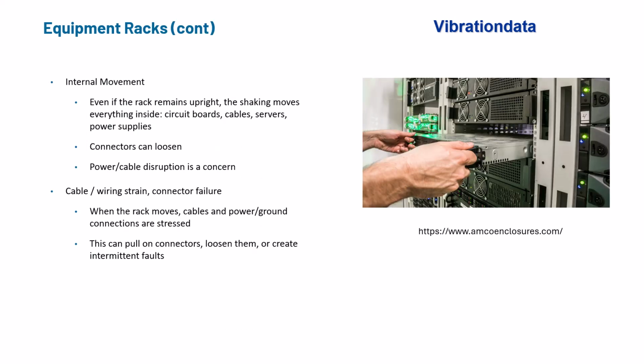So continuing on with equipment racks, these individual electrical boxes are called LRU, for line replacement unit. Our concerns are, even if the rack remains upright, the shaking moves everything inside: circuit boards, cables, servers, power supplies. Connectors can loosen, power cable disruption is a concern. Cable wiring strain, connector failures. When the rack moves, cables and power ground connections are stressed. This can pull on connectors, loosening them or creating intermittent faults.